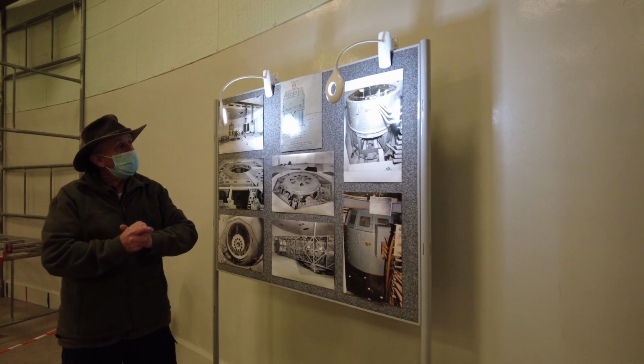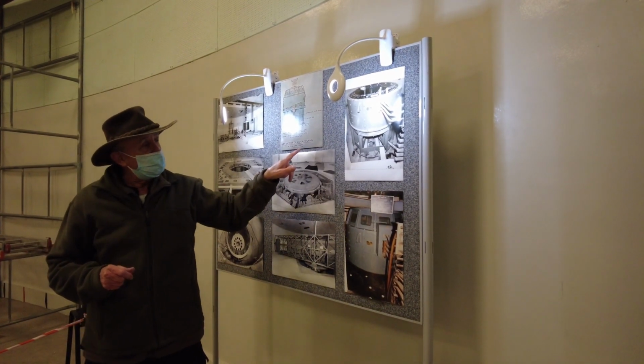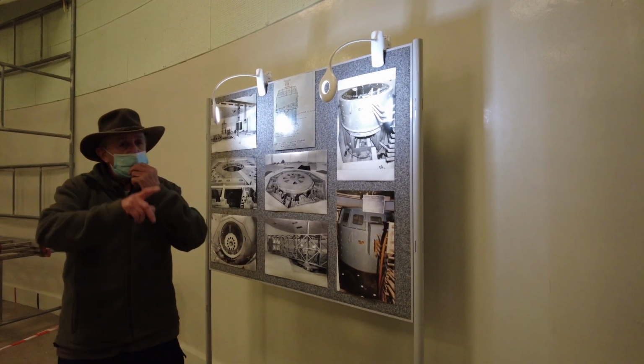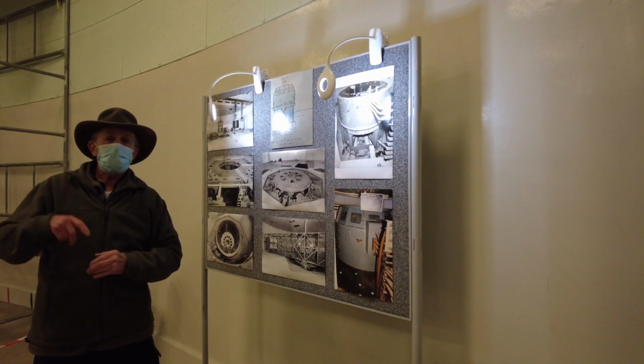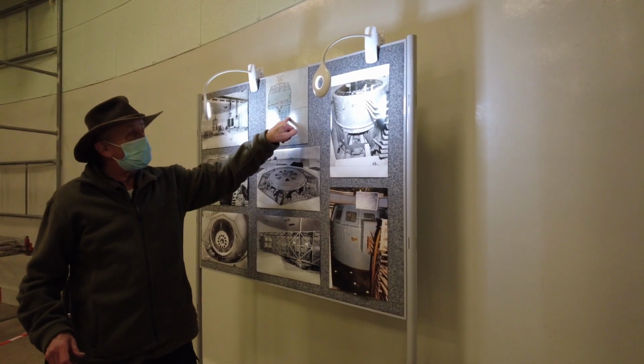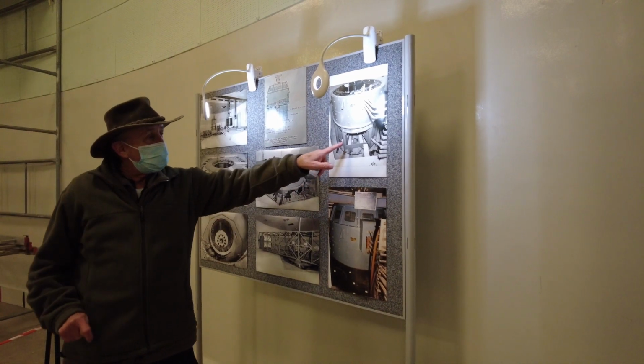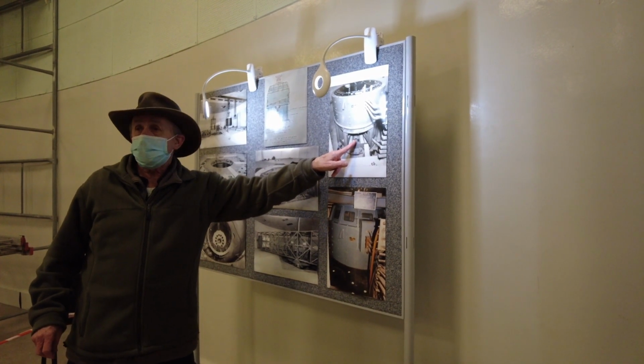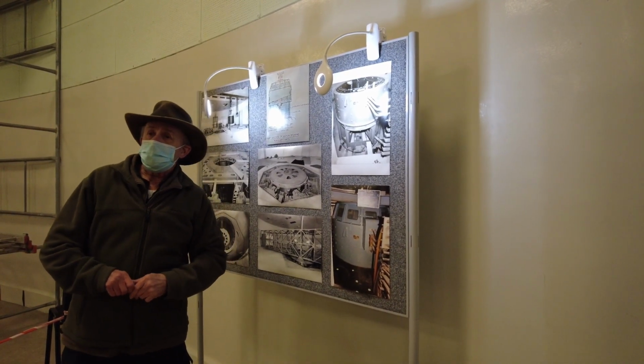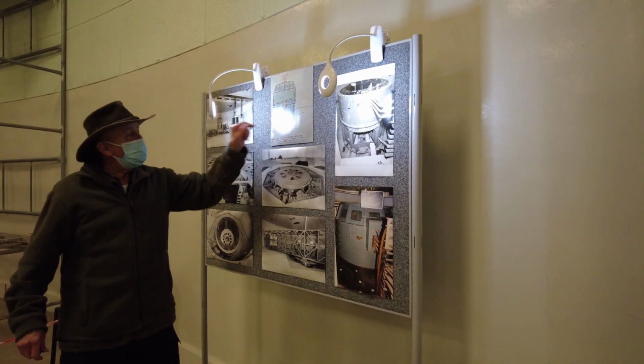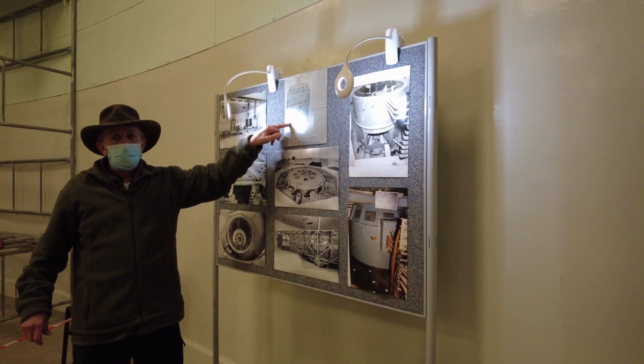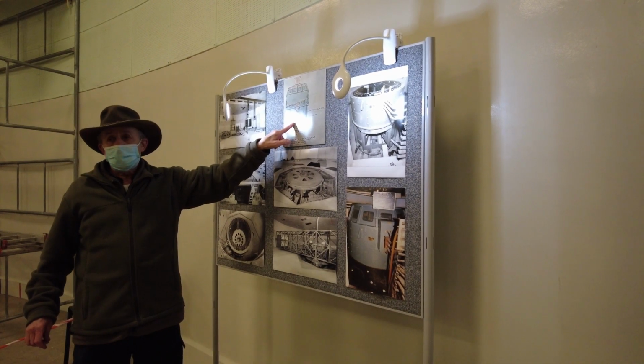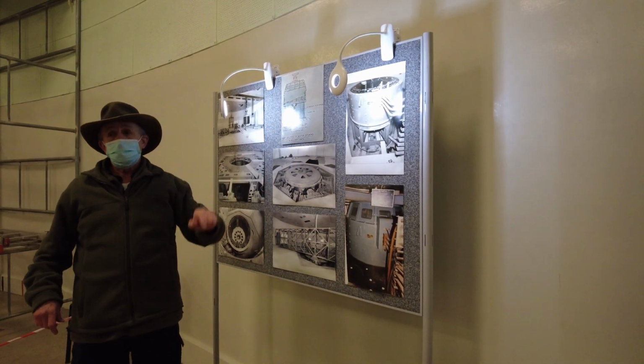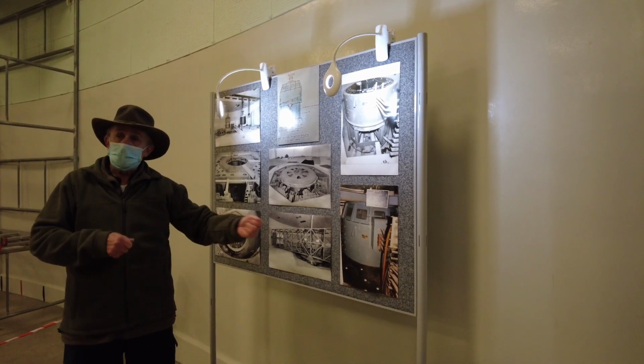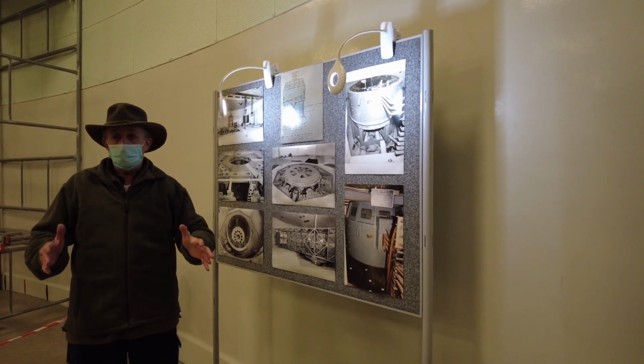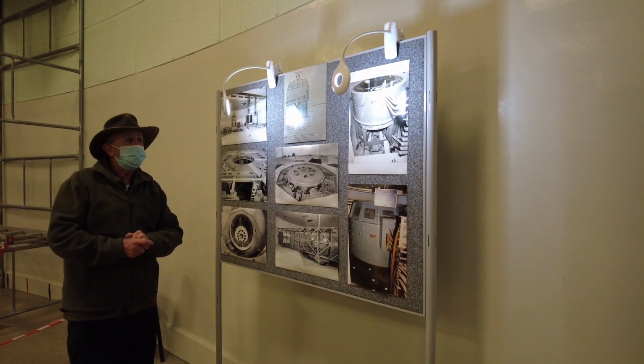One of the jobs we used to do on a regular basis, every 3 months, was for me to go down with a nice big screwdriver, and we'd run the motor generator set. I'd sit down there, they'd buzz down, say right, we're doing 10G - so the single one was a 10G machine going - and just jam the screwdriver into there and trip it, and it'll bring the machine down within 9 seconds. Then you do the 15G and the 30G. The 15 used to be 20, they dropped that down a bit, and then you did the 30. So the machine was going round above my head quite happy, and you just trip them out with a screwdriver on a regular basis to make sure that they work. And we do know they work on that side of things.